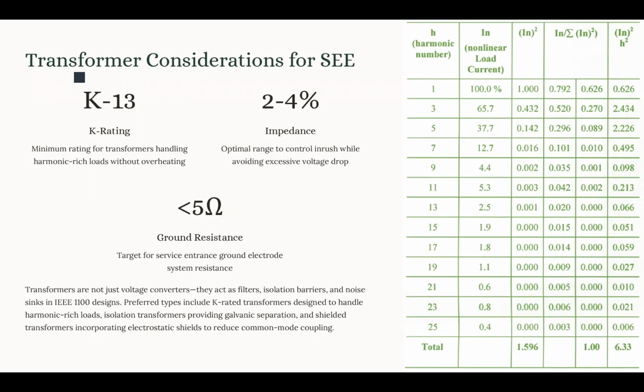Now, we have several criteria for selecting the transformer based on IEEE 1100. One is the K rating, which is for harmonic-rich loads. The K rating indicates a transformer's ability to handle harmonic currents without overheating. We know that harmonic currents are primarily caused by nonlinear loads, and they increase the eddy currents and the losses in the transformer winding and core, meaning you have an overheating problem. In IEEE 1100, the recommendation is a minimum K13 rating for environments with significant sensitive electronic equipment loads.